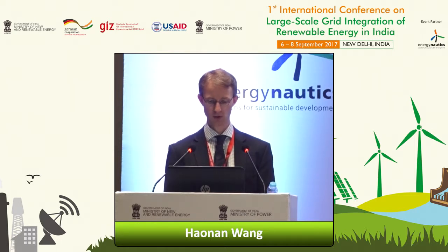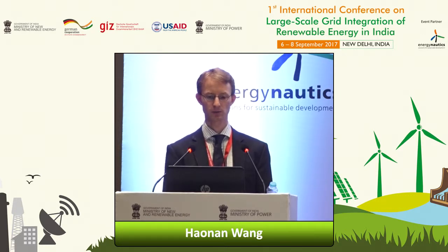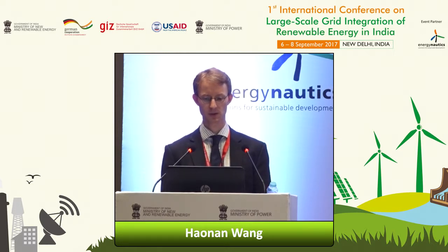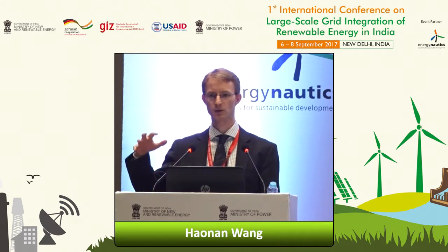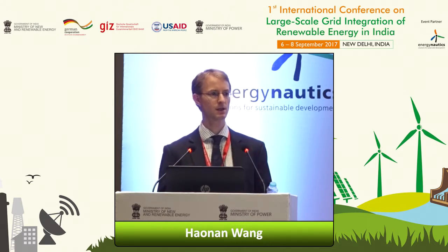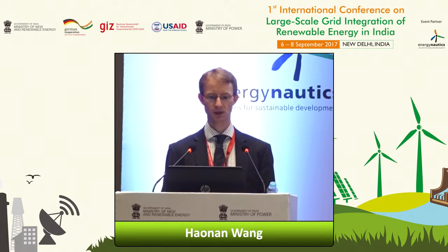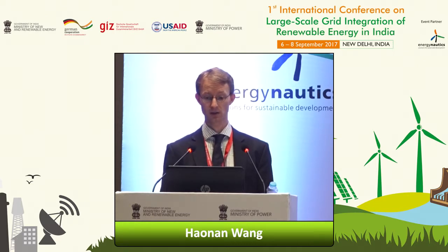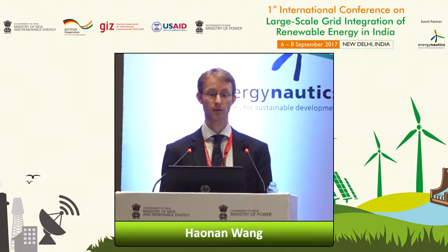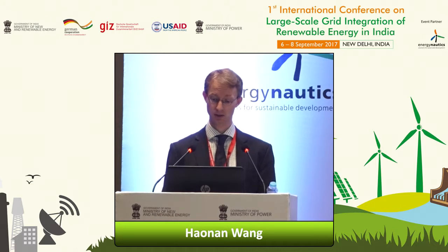This is now first done on reactive power. We have now a follow-up project on active power, actually. We are getting a standard data model, the common information model, CIM, a data model standard for the grids. We extract that from the control center, and then we run our state estimation and optimal power flow calculations, including forecasting. So we can easily test the new DMS functionalities that are relevant and of interest without going really into the control center, specifying, and with very high costs for the operator, bringing some functionality in line.